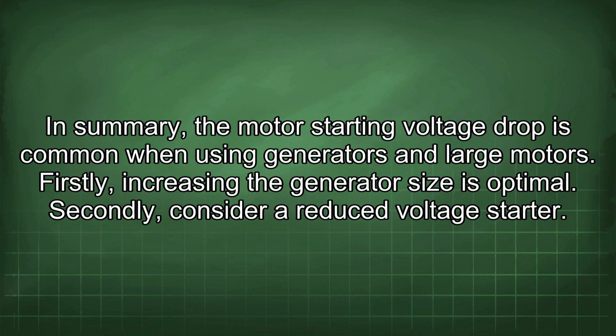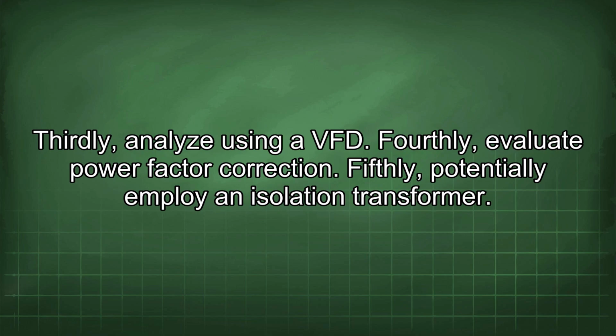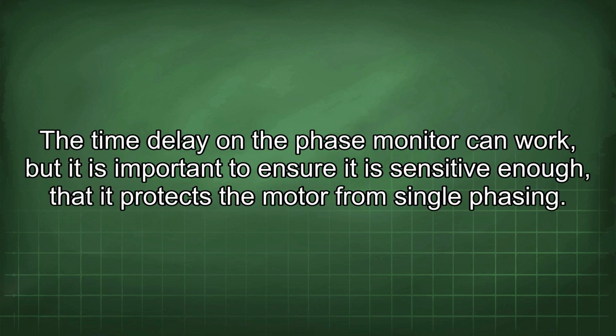In summary, the motor starting voltage drop is common when using generators and large motors. Firstly, increasing the generator size is optimal. Secondly, consider a reduced voltage starter. Thirdly, analyze using a VFD. Fourthly, evaluate power factor correction. Fifthly, potentially employ an isolation transformer. The time delay on the phase monitor can work, but it is important to ensure it is sensitive enough that it protects the motor from single phasing.